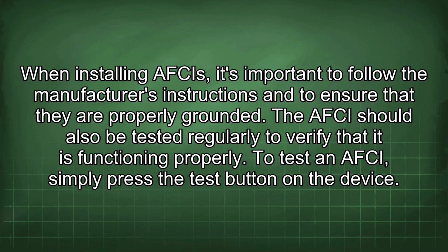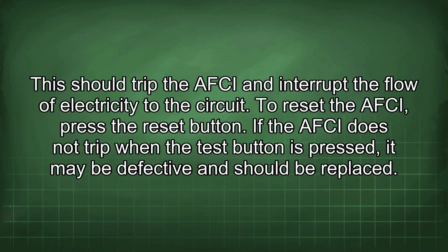To test an AFCI, simply press the test button on the device. This should trip the AFCI and interrupt the flow of electricity to the circuit. To reset the AFCI, press the reset button. If the AFCI does not trip when the test button is pressed, it may be defective and should be replaced.